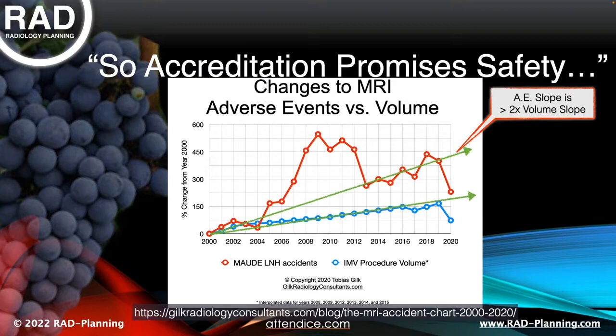So does the hospital call GE, Siemens, Philips, whoever, every time there is an adverse event in their facility and say, hey guys, we want to let you know, we almost killed somebody. Would you please kindly tell the FDA? There's no obligation for the healthcare provider to tell the manufacturer. There is a requirement, if the manufacturer is made aware, that they have to report it to the FDA. It's always been a gray area. If we can't even agree what a serious injury is, how on earth are we going to agree what an unreasonable risk of that is?